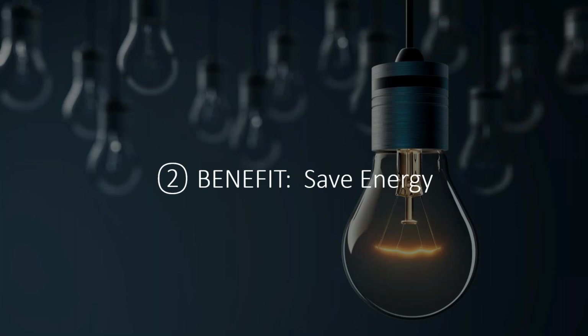All right, so we talked about, hey, it's important to bring in the proper amount of outside air, comply with your codes and standards that are built upon providing proper indoor air quality. But we also don't want to bring in too much, right? Because the cost to condition outside air can be expensive. The Department of Energy states it can be anywhere from $2 to $9 per CFM.